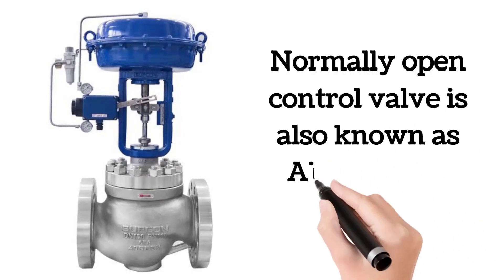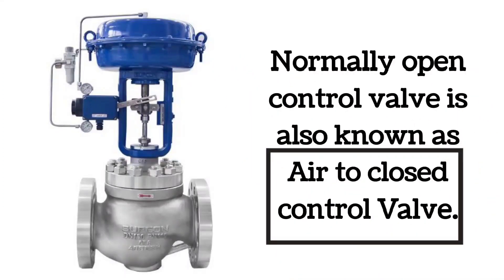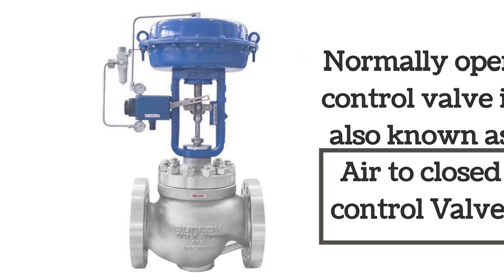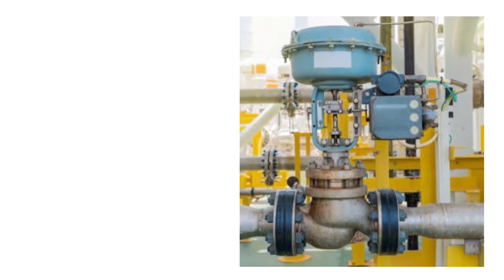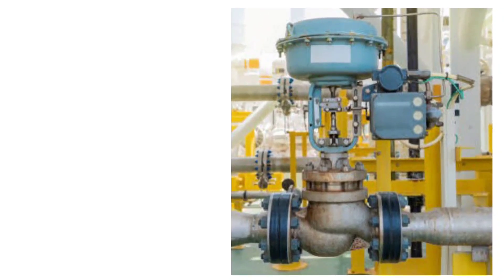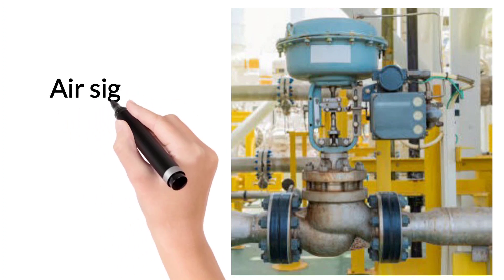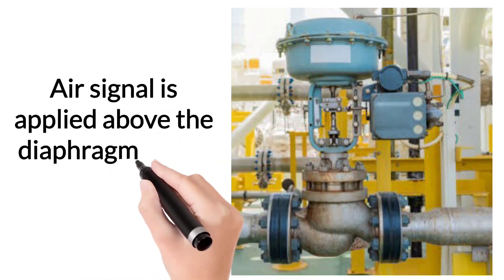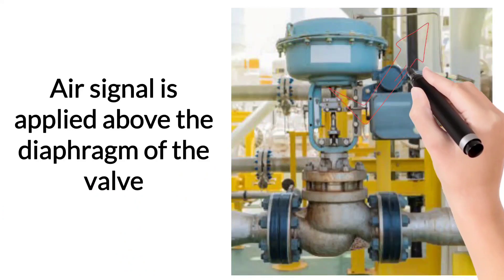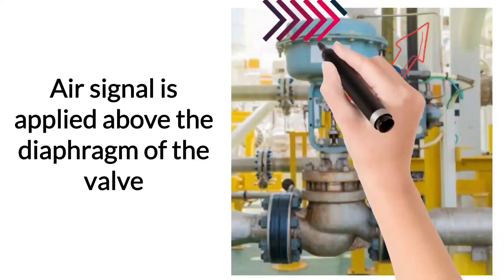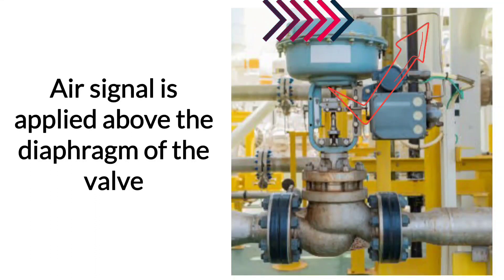A normally open control valve is also called an air-to-closed control valve. In the image, you can see a normally open or air-to-closed control valve where the air signal is applied above to the control valve diaphragm. When an air signal is applied over the diaphragm, the control valve starts closing — that's why it is called an air-to-closed control valve. In the absence of air, this valve remains open, hence it is called a normally open control valve.